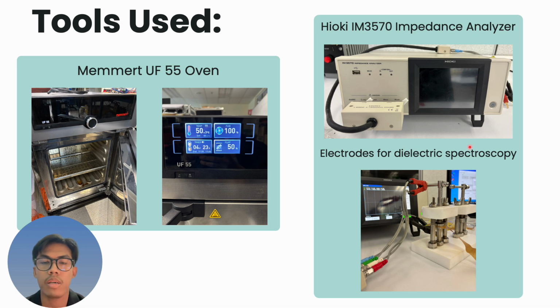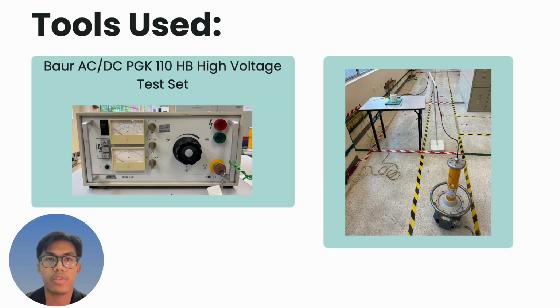The second tool is the Hioki IM3570 impedance analyzer, used for dielectric spectroscopy. So it provides accurate measurements of relative permittivity and loss tangent across a wide frequency range. The third tool is the AC-DC high voltage test set for BDV test, which applies high voltage to determine the breakdown strength of the oil impregnated paper. So this test helps evaluate the insulation's electrical endurance.